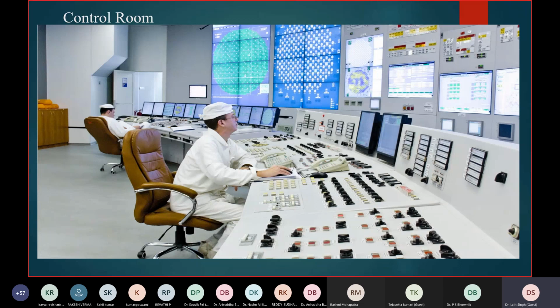So what is happening is there is a sensor, an electronic sensor, which is capturing data from the field, probably the temperature or pressure of a particular component. These signals are basically raw signals, and they may be analog signals or digital signals. For example, if I am interested in looking at the level of a tank, that is definitely an analog parameter. And if I am interested in whether my valve is open or closed, that is a digital parameter, because it is either 0 or 1. It has finite states, whereas analog means it has infinite states.